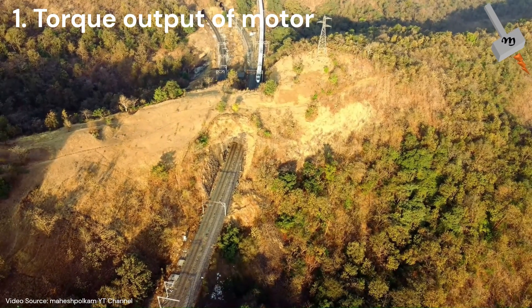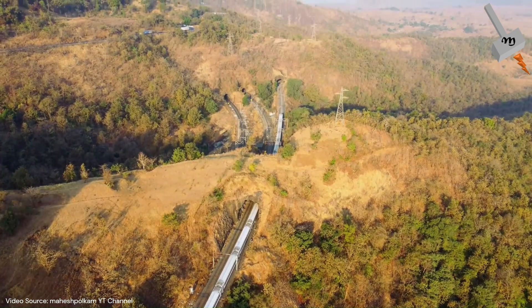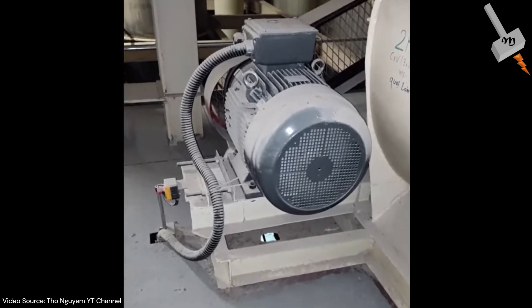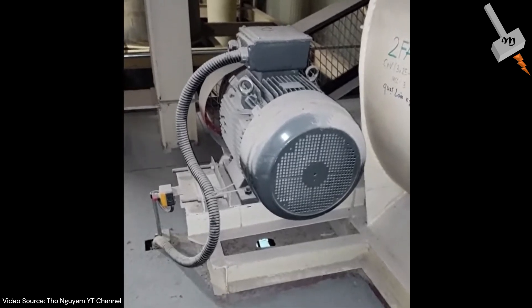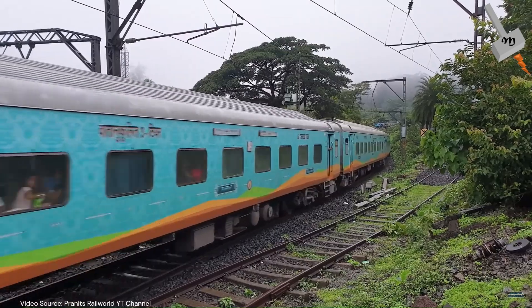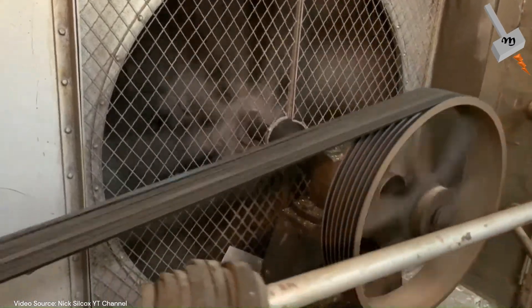For example, for temporary acceleration and hill climbing, traction motors need to offer the maximum torque that is 4 to 5 times of the rated torque for overload operation. Now being a locomotive application, traction motors need to achieve 4 to 5 times the base speed for cruising, while industrial motors generally achieve up to twice the base speed for constant power operation.